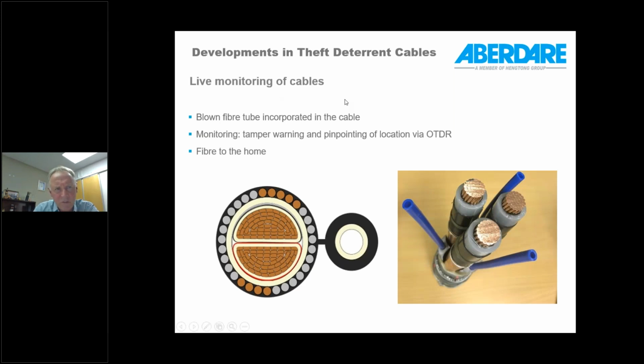If we move on to live monitoring of cables, we experimented with some alternative configurations of cables, in essence providing a blown fiber capability which can be incorporated into these cables. The idea is that you can install a cable with this facility and only at a later time use the installed facility to blow in fibers, and then to either monitor for heat or for tampering by these systems. You can also install fiber to the home in low voltage applications. So it has a number of potential applications.